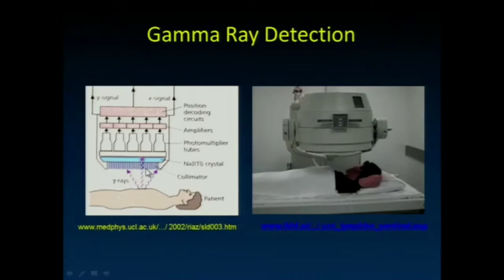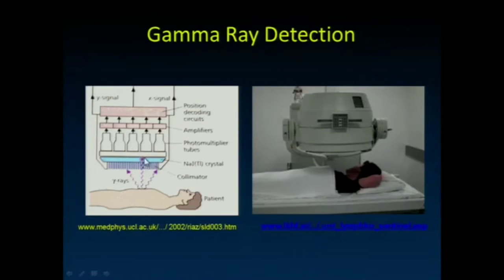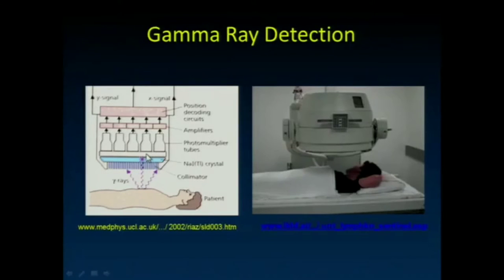It's really the collimator that acts as a lens to focus the radiation, accepting it only along a particular direction. Beneath that is our sodium iodide crystal. When a gamma ray interacts in the crystal, we get the production of lower energy visible light, which is readily detected by our photomultiplier tubes. Unlike x-ray imaging, we have very small detector elements because we need high resolution imaging, but we image over a longer period of time.